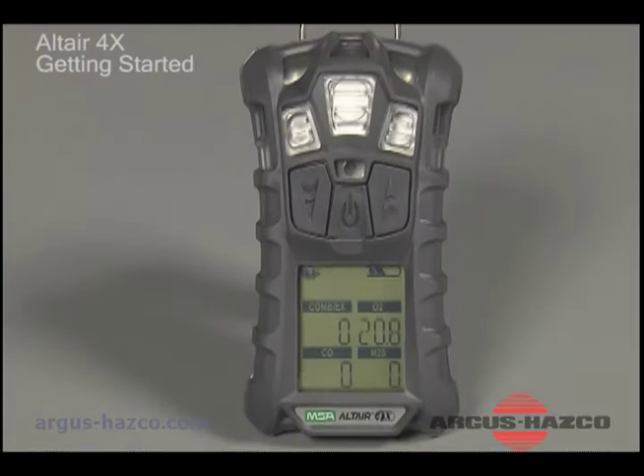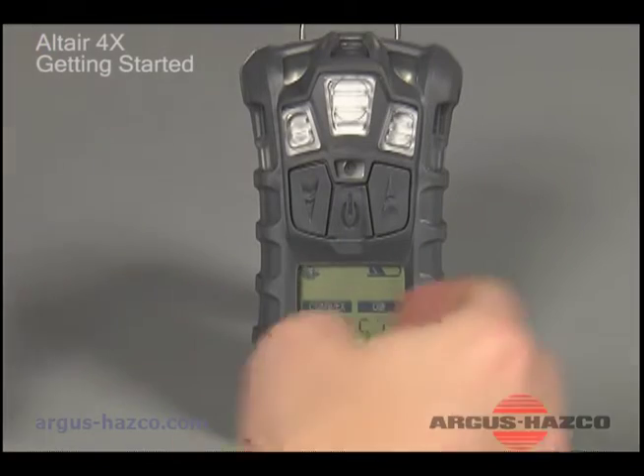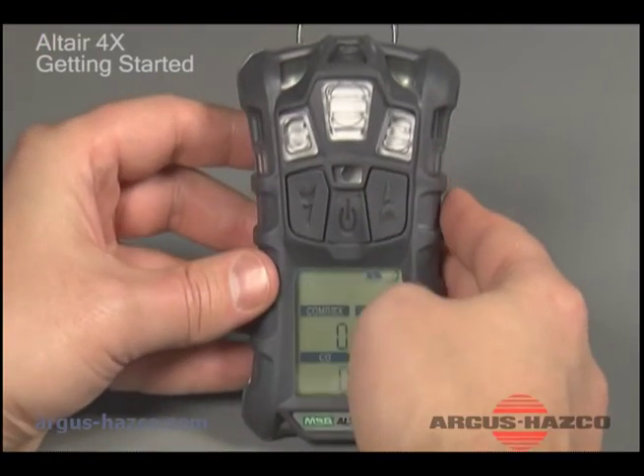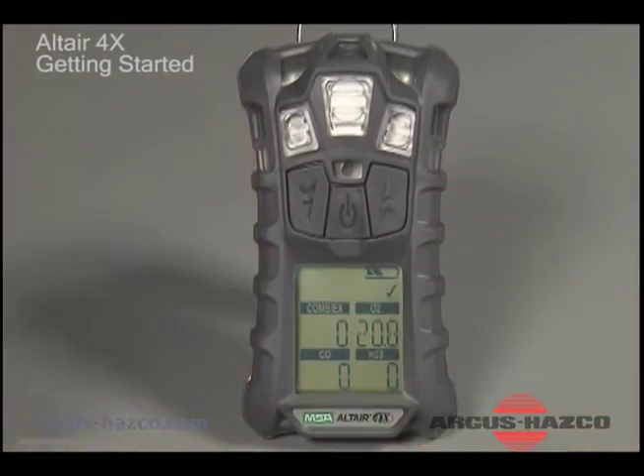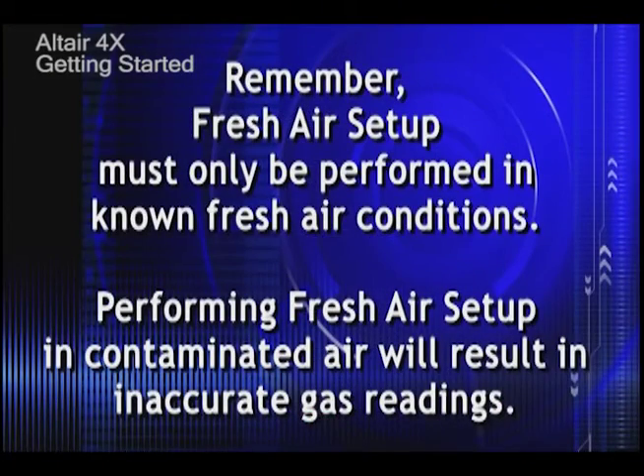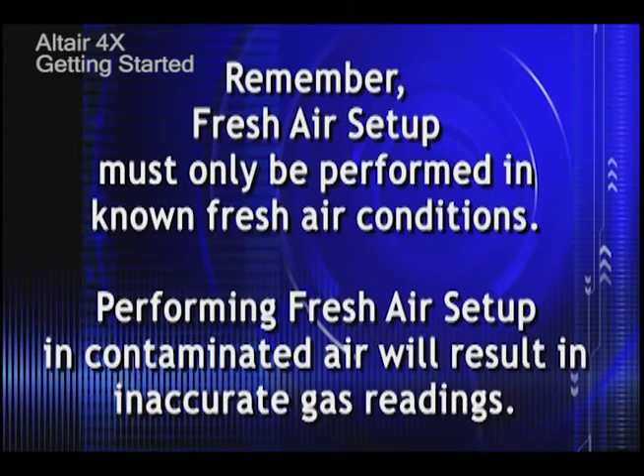To skip Fresh Air Setup, push the Page Up button or simply wait 10 seconds. Remember, Fresh Air Setup must only be performed in known fresh air conditions. Performing Fresh Air Setup in contaminated air will result in inaccurate gas readings.